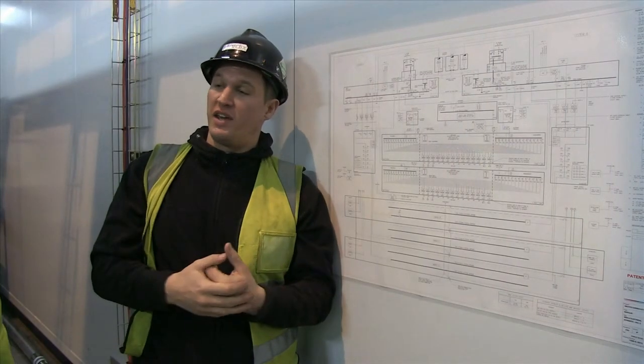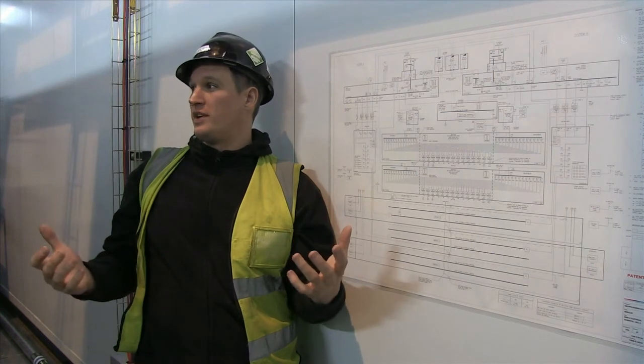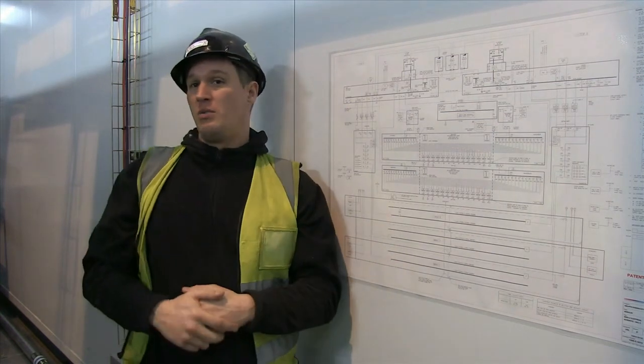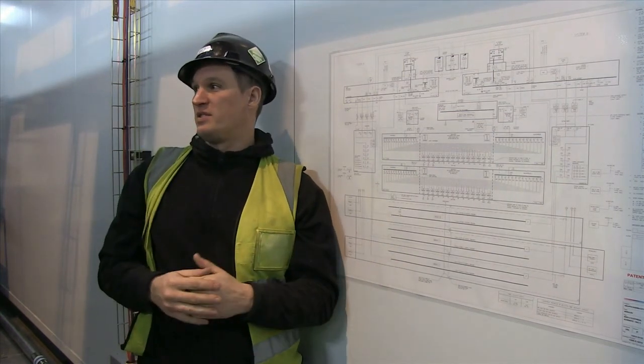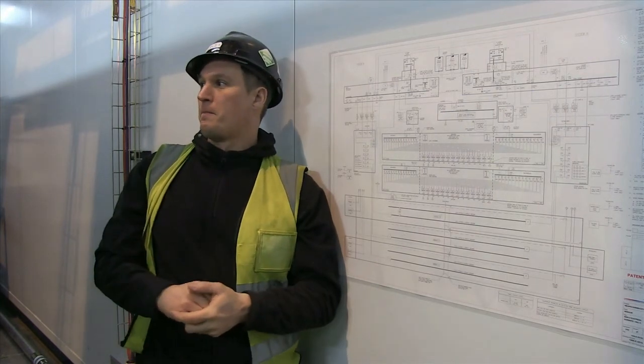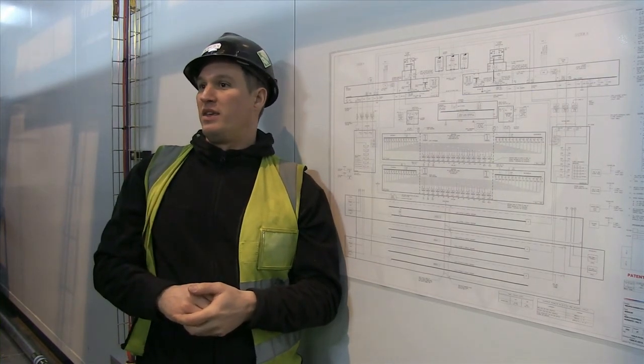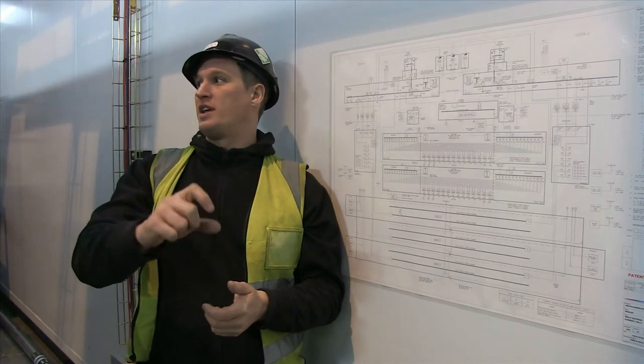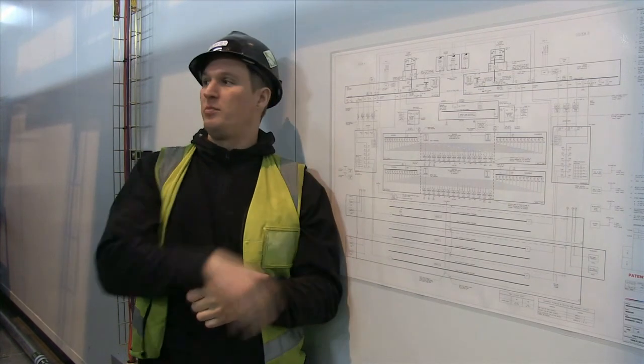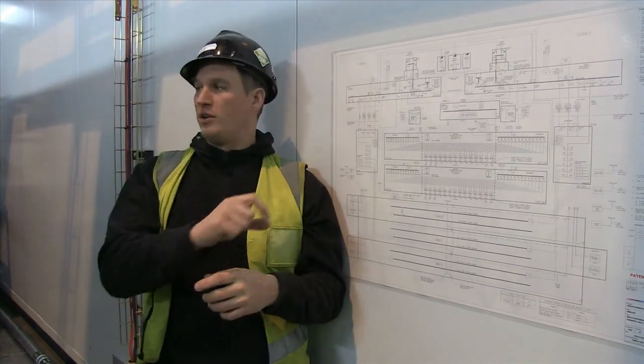It's the removal of the key to put it in maintenance bypass, but I'm sure you've done it so many times, and the Socomec guy will go through it. He's got to put it in static bypass. It's not something I've just, first time we've had a maintenance bypass. I'm sure we'll get it there. If you do go and force the key out, as I'm sure you're aware, you'll take all of the UPSs out. There's a contact on the back and it will shunt all of the UPSs out.